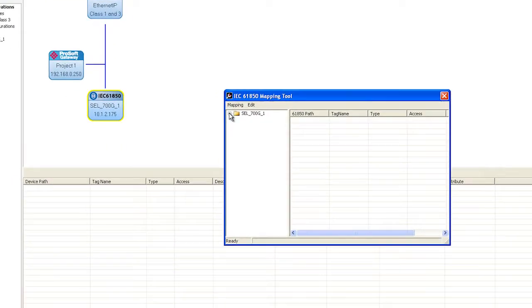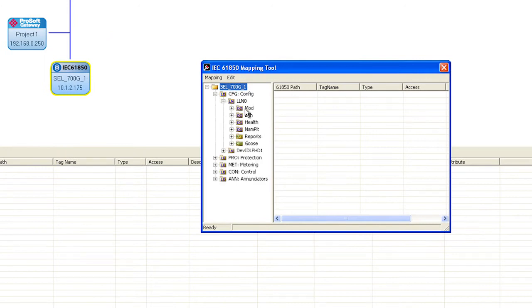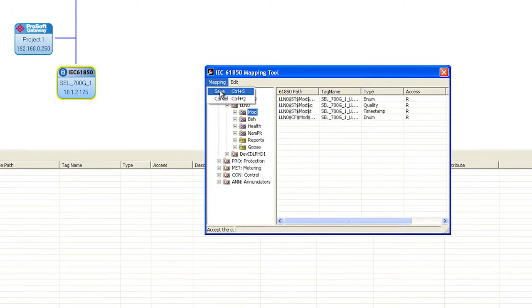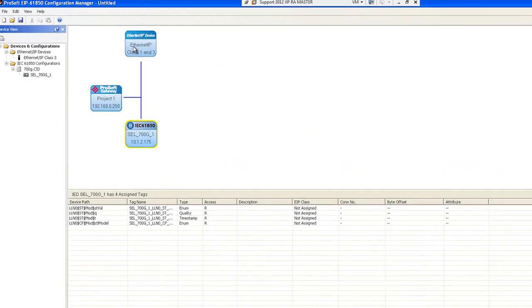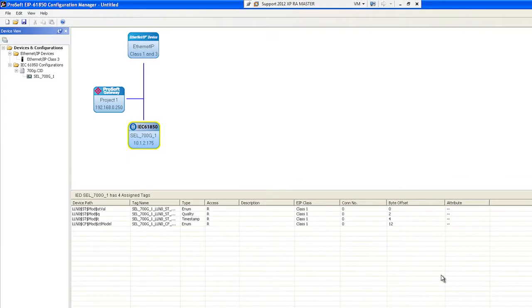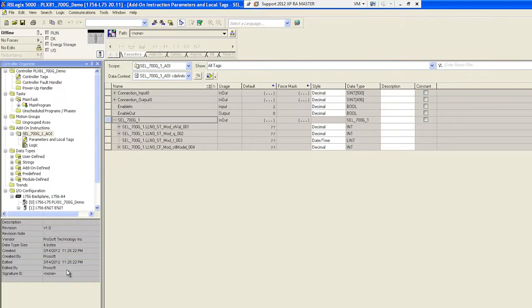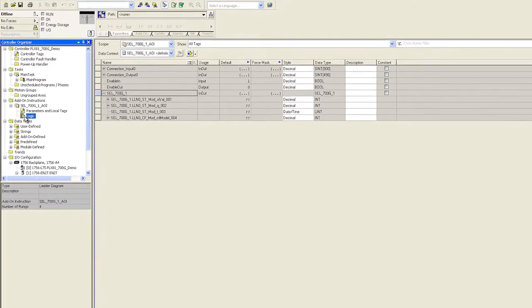Select the data points that you want to obtain from that 61850 server, assign the data points to an Ethernet IP I.O. connection, and download the configuration file to the module.